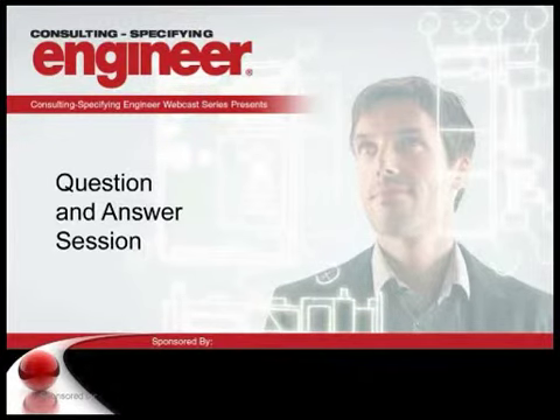Yeah. The generator will put out based upon the subtransient reactance in the initial cycles, and it'll go for a little bit, and then the PMG will kick in. And that'll kick in so that your maintained fault will not decay less than 300%. It doesn't mean that your fault is 300%. Your fault is actually a lot more than 300% at the initial phase, but it'll decay to that point and allow your breakers to trip.